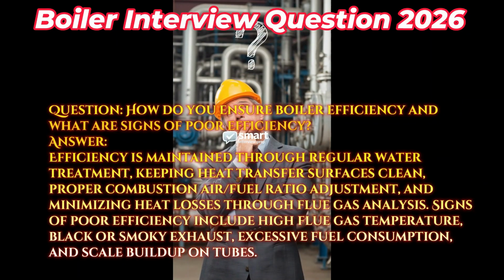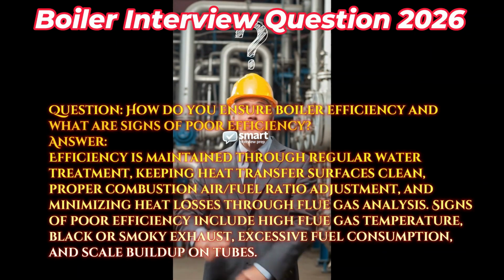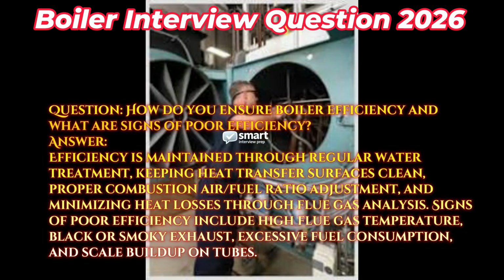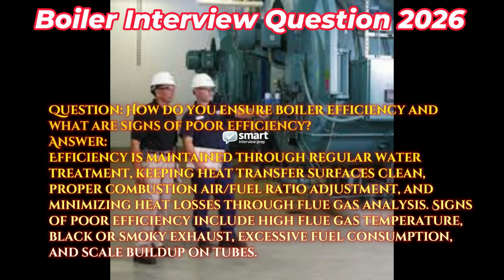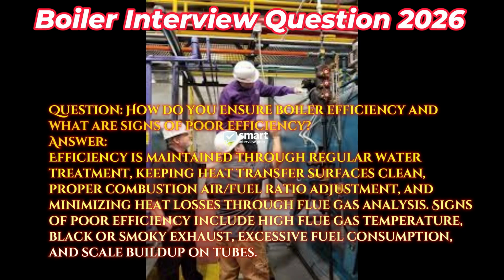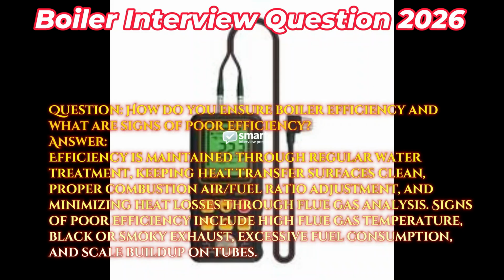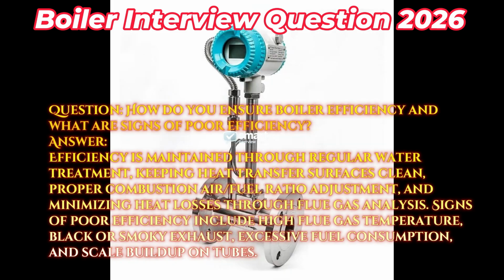Question: how do you ensure boiler efficiency and what are signs of poor efficiency? Answer: efficiency is maintained through regular water treatment, keeping heat transfer surfaces clean, proper combustion air/fuel ratio adjustment, and minimizing heat losses through flue gas analysis.